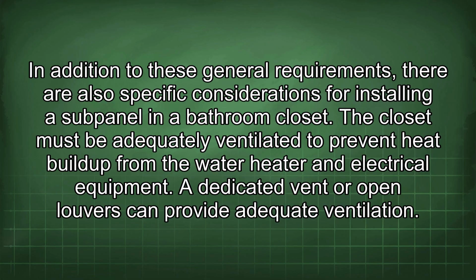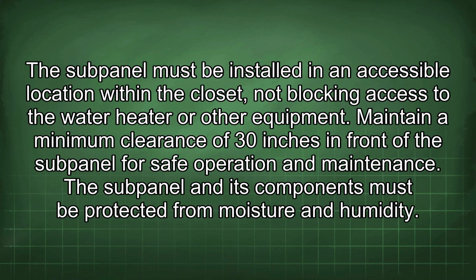In addition to these general requirements, there are also specific considerations for installing a subpanel in a bathroom closet. The closet must be adequately ventilated to prevent heat buildup from the water heater and electrical equipment. A dedicated vent or open louvers can provide adequate ventilation. The subpanel must be installed in an accessible location within the closet, not blocking access to the water heater or other equipment. Maintain a minimum clearance of 30 inches in front of the subpanel for safe operation and maintenance.